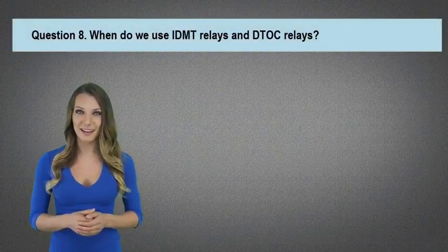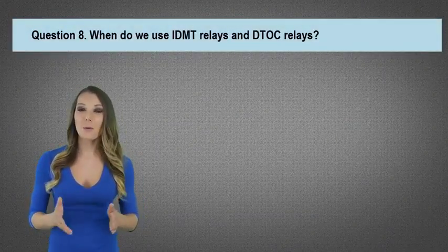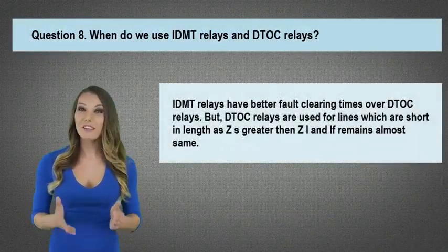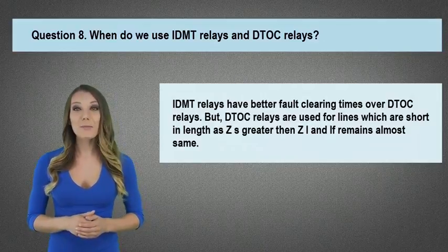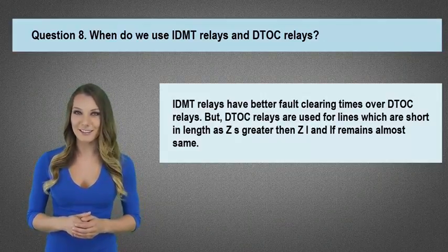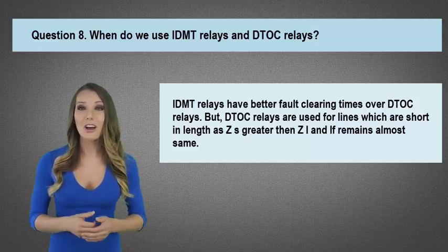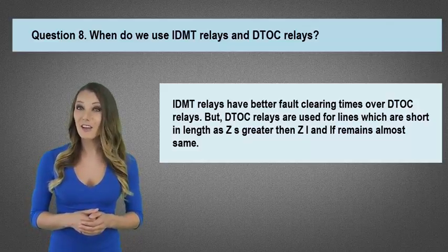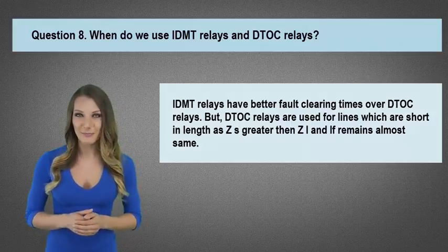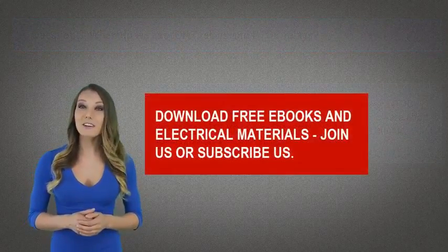Question 8. When do we use IDMT relays and DTOC relays? IDMT relays have better fault clearing times over DTOC relays. But, DTOC relays are used for lines which are short in length, as ZS is greater than ZL and If remains almost the same.